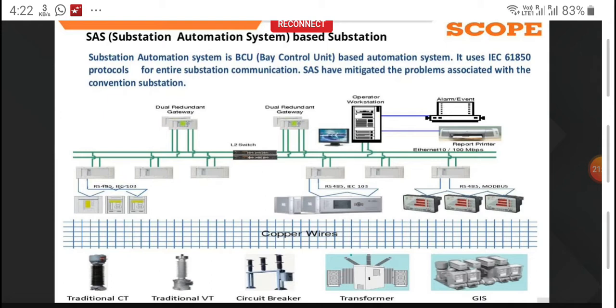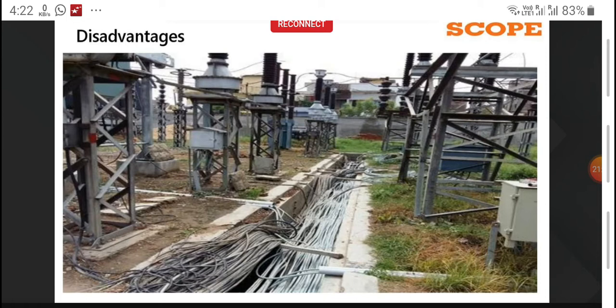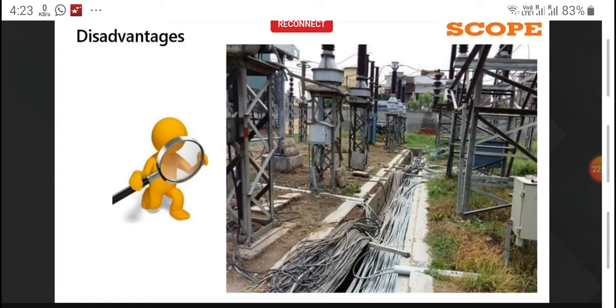But before going to the digital substation, I just want to look at the disadvantage. The main disadvantage of these substation automation SAS-based substations is that you are still using copper cables. It is again a problem, because in most electricity boards the copper cables running through the trenches are in very bad shape. Over the period, because people do not maintain those copper cables or the trenches, after some years these cables are messed up with each other, and you cannot understand which copper cable belongs to which bay, or which cable belongs to which signal. So it is very difficult for a site engineer to recognize, and if any problem comes, it is very difficult to trace the cable. That is the main issue with the copper cables.